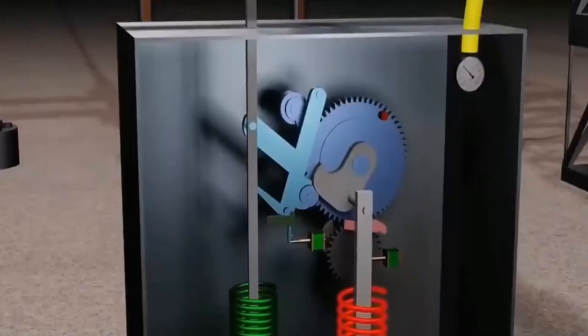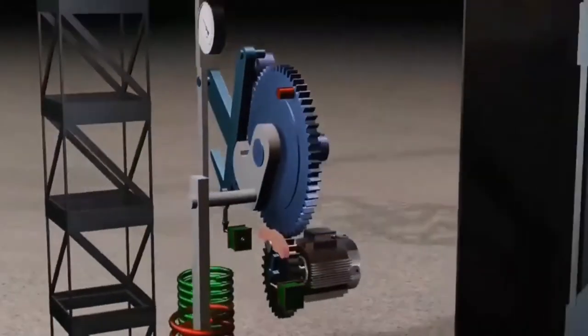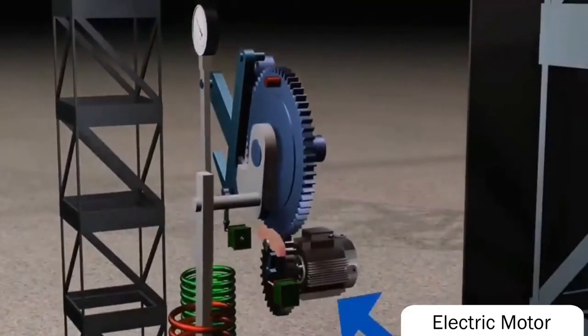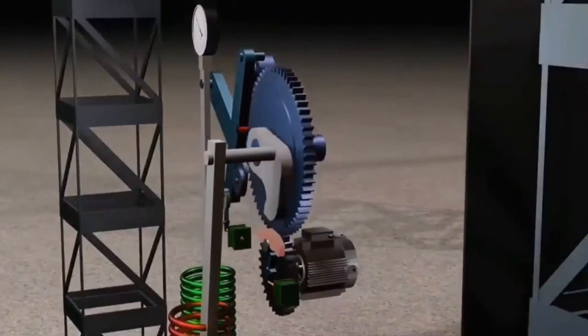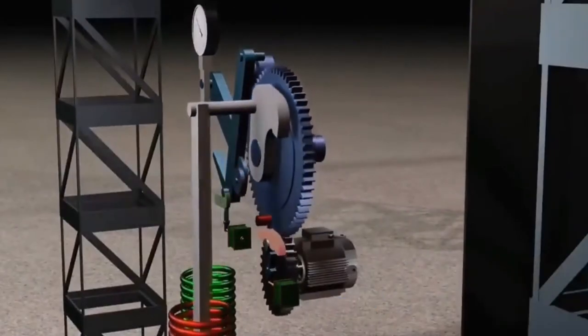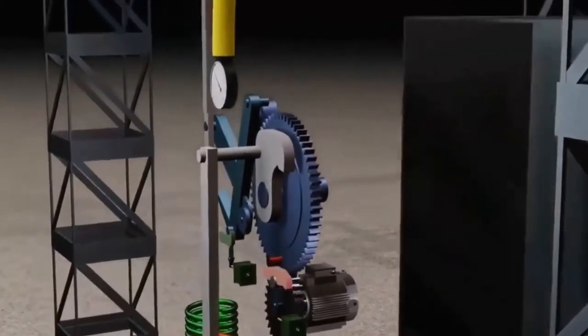However, there's an issue: the pressure of the spring on the right side is already released, so how to reset it? Actually, it's simple, there is an electric motor behind the circuit breaker. When the circuit breaker closes, the electric motor will drive gears to rotate, resetting the spring on the right side.